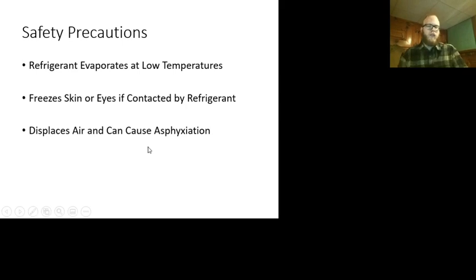That's going to require a trip to the hospital or a doctor. Also, something that is really important to realize is the refrigerant in a system, once we release it, because it's going to expand so much turning into a vapor, it can displace the air inside of a small space. If you're working on a car and you disconnect a hose and you're in a one bay garage that's completely closed in, you'd want to open the door and leave the area, because you could actually pass out because so much of your oxygen has been displaced. If you're in a big shop, it's just going to smell real bad and everybody's going to dislike you, and you've also not done great things for the atmosphere, environment. But you're not likely to pass out because of it.